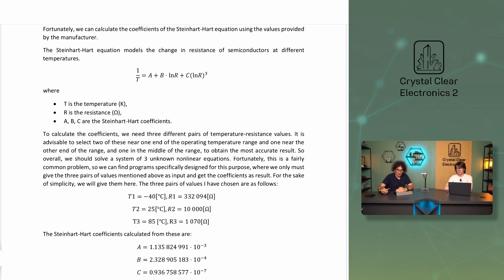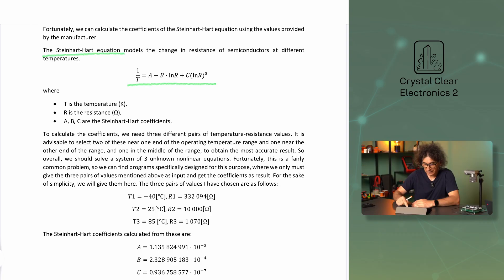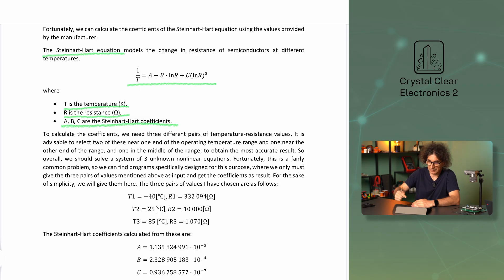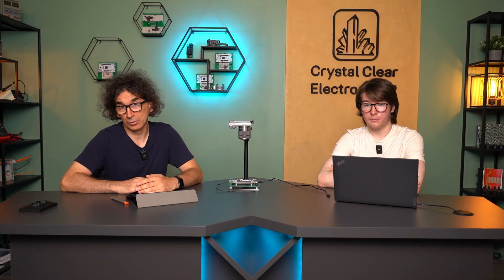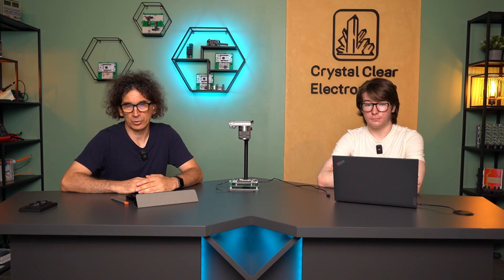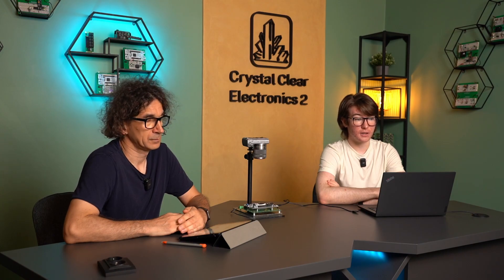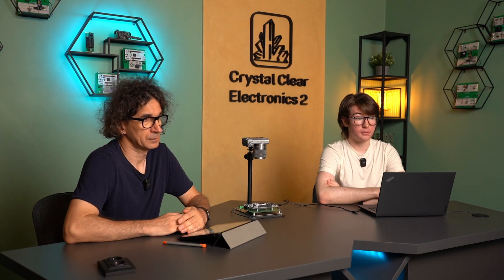Using the values provided by the manufacturer, we can calculate the coefficients of the Steinhart-Hart logarithmic equation that models the variation of the resistance of semiconductors. In the equation, capital T represents the temperature in Kelvin, capital R is the resistance, and capital A, B, and C are the Steinhart-Hart coefficients we are looking for. To calculate the three coefficients, we need three different pairs of temperature-resistance values. It is advisable to choose two near the edges of the operating temperature range and one in the middle, to get the most accurate result. Overall, we solve a system of three unknown non-linear equations — programs specifically designed for this purpose are available where we only need to input the three pairs of values and receive the coefficients as output.